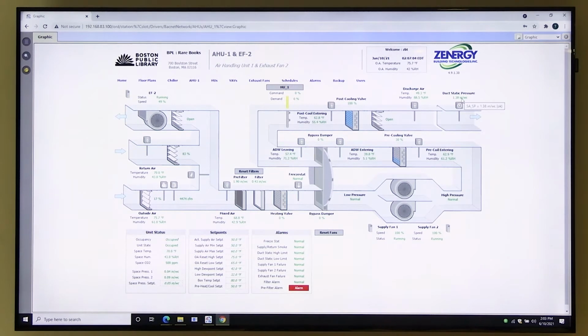As far as normal operation, we were talking about how that VAV system works, where the dampers open and close as needed, and the fans modulate to make sure we have that airflow, monitoring the pressure in the ductwork. That's this sensor right here, the supply air static pressure. If the fans aren't running, that's going to read 0. But if this sensor fails, it's going to have an issue with the fans. The fans are going to have a problem.